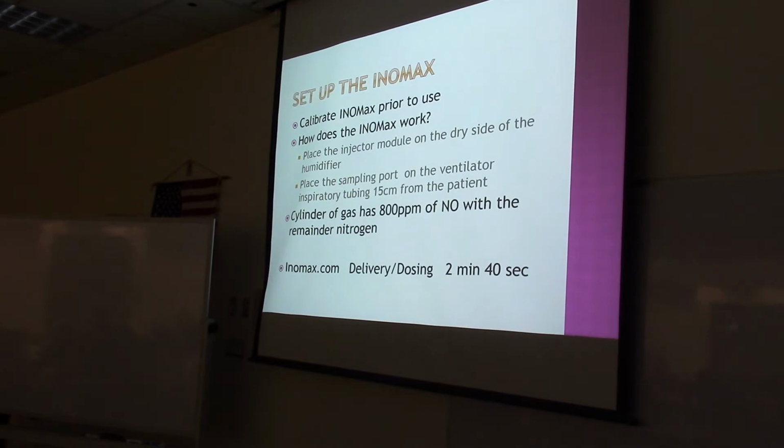When you're setting up the INOmax, you have to calibrate it first before you use it. And then how does it work?